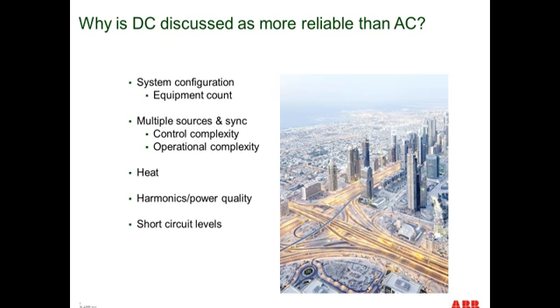As Frank indicated, heat means lost energy and requires treatment. So the less heat you put into the system, the less heat you have to remove or cool, which may simplify your mechanical system. And by being able to parallel DC, as Frank indicated, you have fewer complicated control systems by not needing to synchronize those multiple sources.